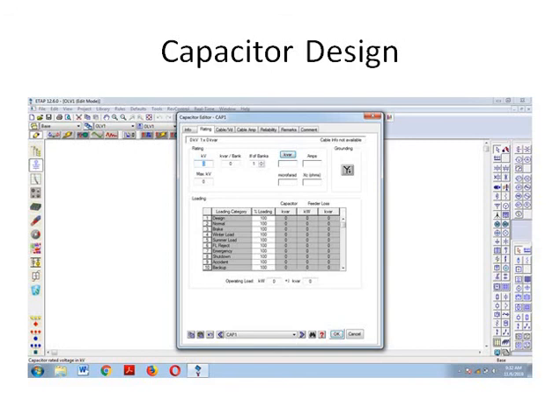Like increasing system capacity and reducing system losses in our system. A lagging power factor can lead to increased heating losses also. So considering all these aspects, it's very important to maintain the power factor in the desired limit and make use of modern electrical software to evaluate the performance after implementation of a particular capacitor bank.